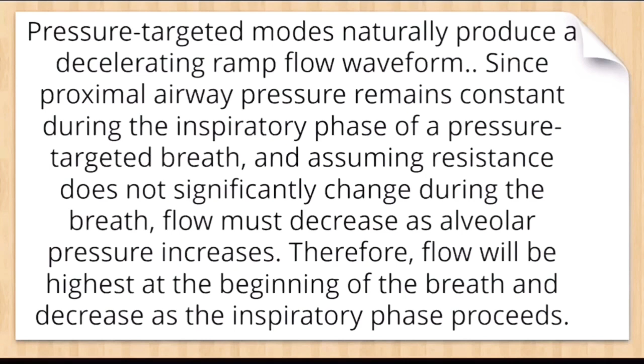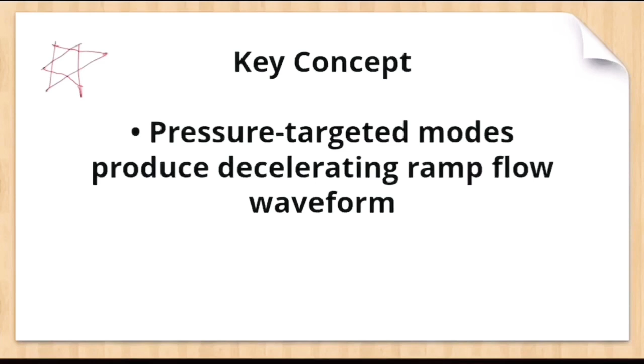Now key concept, pressure targeted modes produce decelerating. Just remember it. If you have selected pressure targeted mode, if you have selected the pressure target, then what will happen to the waveform pattern? You don't have to select either. In case of flow, we can select either the square waveform pattern or the decelerating waveform pattern. But in case of pressure targeted, they naturally produce a decelerating waveform pattern.